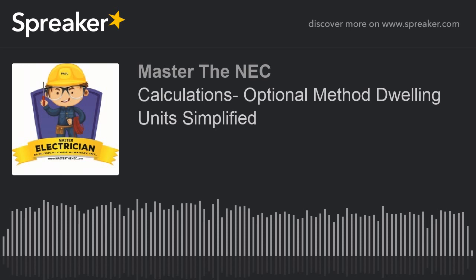So we add up the general lighting receptacle loads, which is 7,500. We add up the two small appliances, with 3,000. We add up the laundry, which is 1,500. And we add up all of the appliances. You just add them all together, and that was 22,328. Add all those up together, and we end up with 34,328. So that right now is the total sum of all four of those values that we added up.